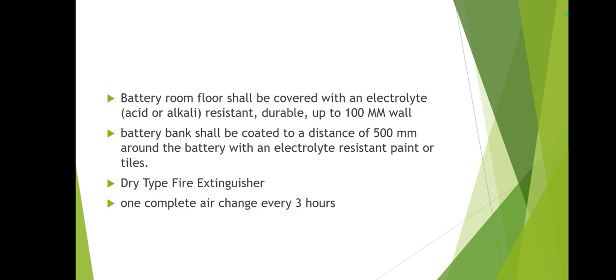These are NEC questions. Wherever we use a battery bank, suppose we are going to install the battery bank near the wall — that area should be coated up to 500mm around the battery with electrolyte resistance paint.